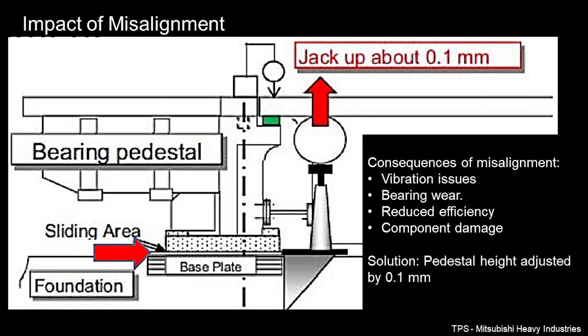So what's the impact of misalignment? Misalignment can cause vibration issues, bearing wear, reduced efficiency, and component damage. To fix this issue, a 0.1 mm adjustment was made to the bearing pedestal to correct the alignment.